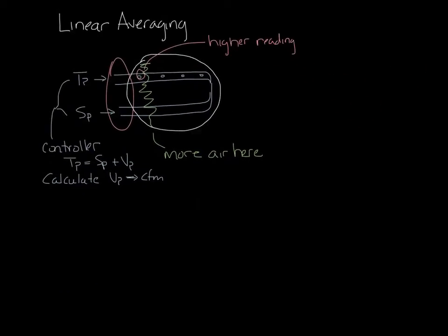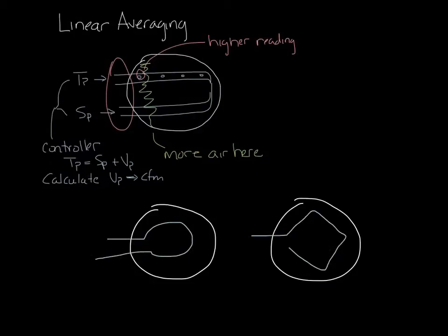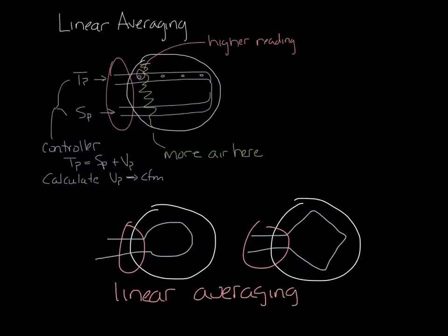Okay, so let's move this up a little bit out of the way. One thing to note is that linear averaging sensors don't have to be linear in shape. Many linear averaging sensors are round or diamond shaped. They look kind of like this. Let's draw the inlet. This one has a round sensor in it. Another inlet, this one has a diamond shaped sensor in it. But you can see that the sensor readings are taken over here on one side, so they are linear averaging. So if the airflow comes down the side of the inlet, just like above, the holes on that side are going to read higher, and it'll again skew the information coming out of your sensor.